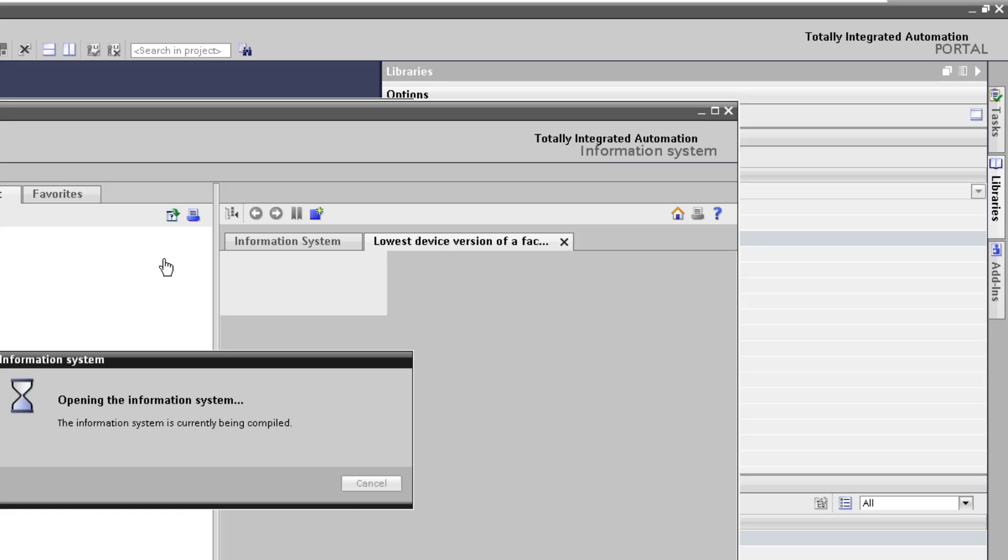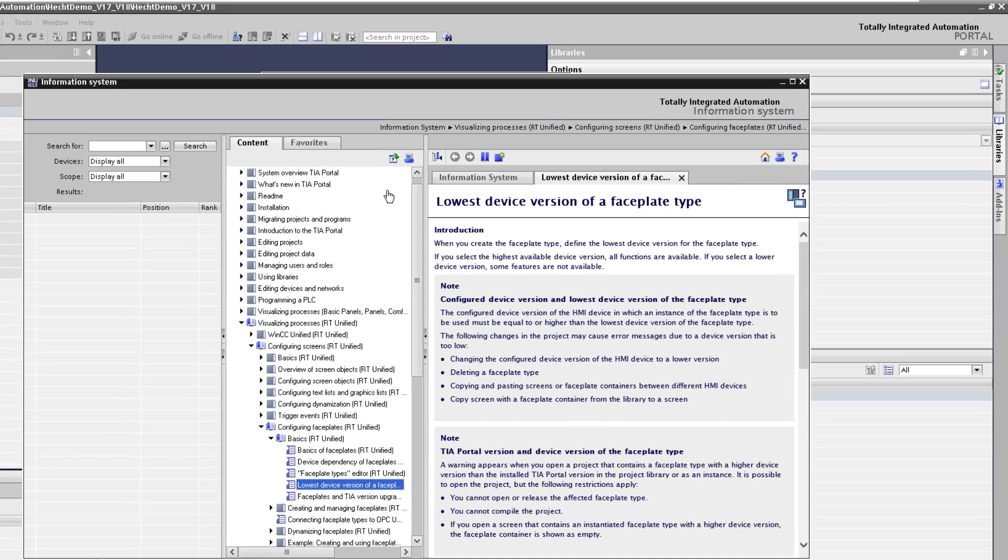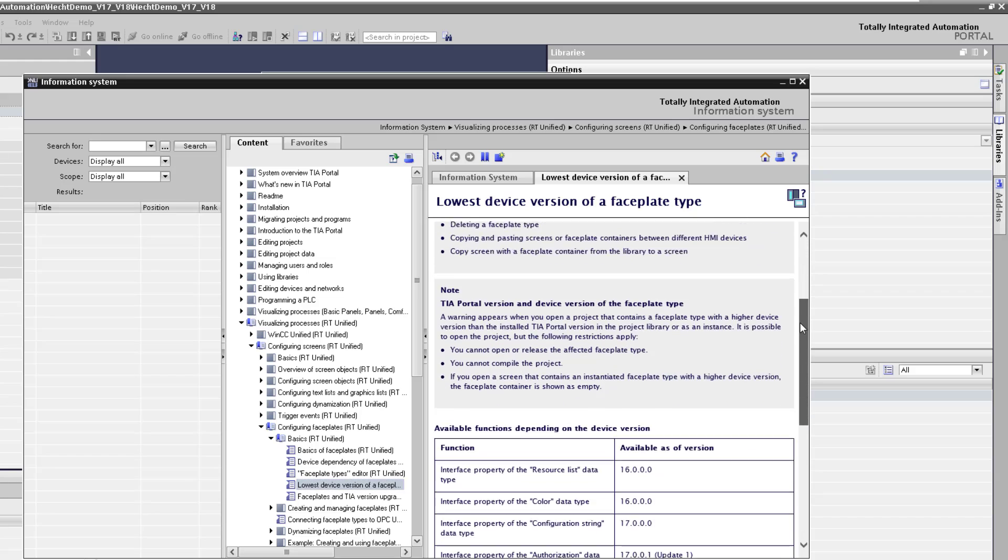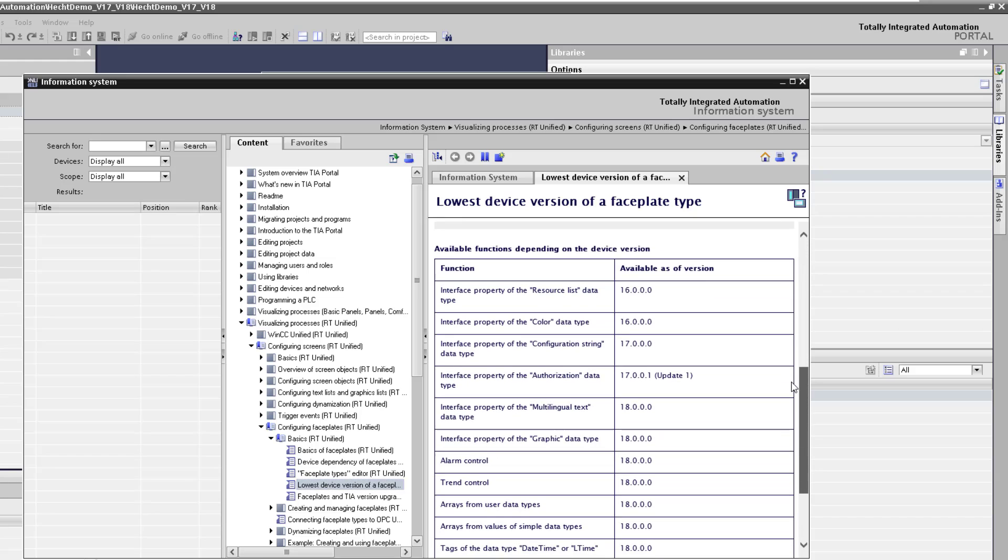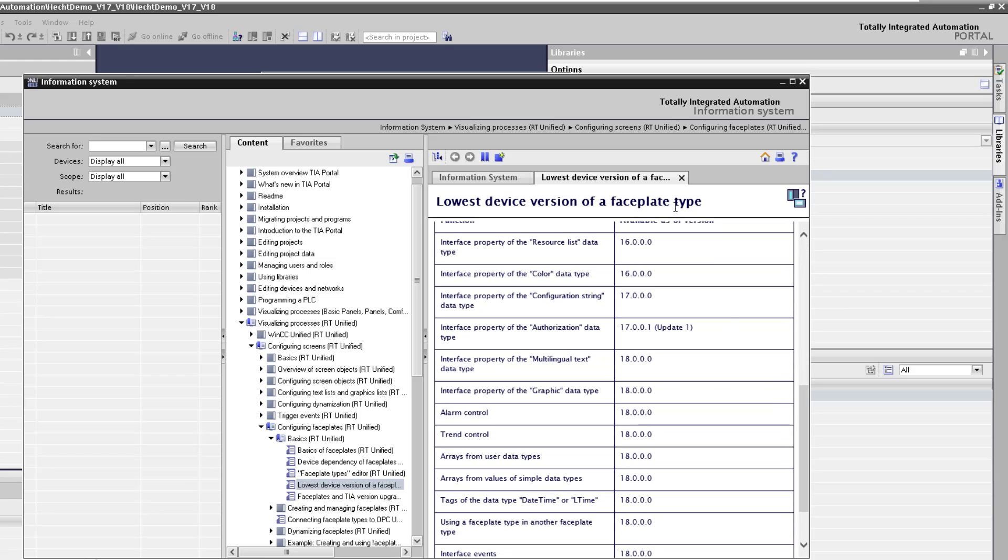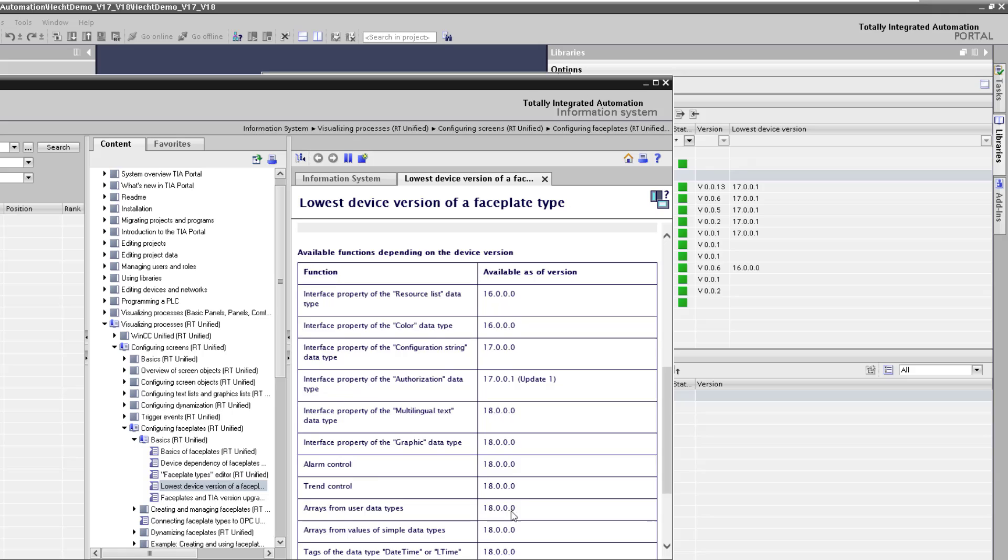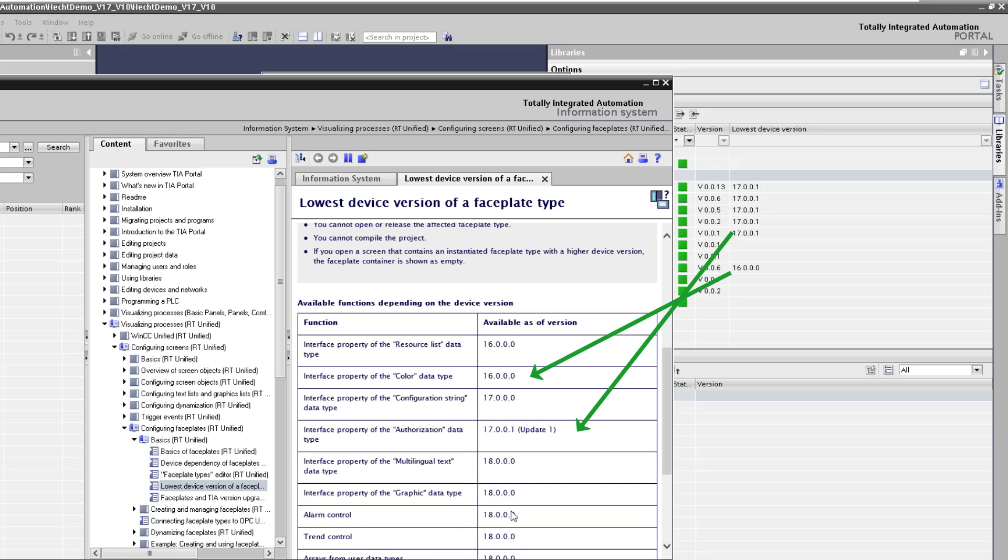And if you check the help you will see an overview of which functionality of a faceplate is available in the version of the faceplate. And you see for example with the update 1 there was this new authorization interface. I used this. That's the reason why I have here V17 update 1. And in this faceplate from the V16 I have only functionality from the V16.